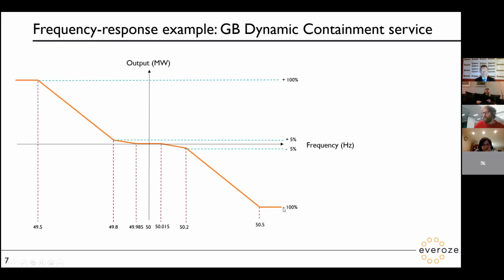This orange line reflects what these projects are supposed to be trying to do to combat varying frequency. When the grid frequency is high, there's too much generation and too little demand, so they're commanded, and actually paid, to import power and charge up at varying amounts until they hit 50.5. At very low frequencies, they're paid to export power, to discharge. In this particular case it's called dynamic containment, which is the main one at the moment in GB. In the middle they do very little, it's really designed just to show that they're still working, which is why there's this tiny little ramp here.